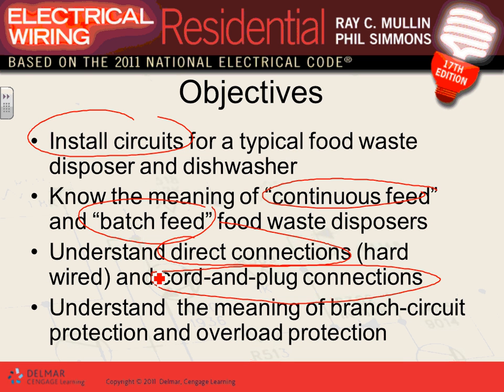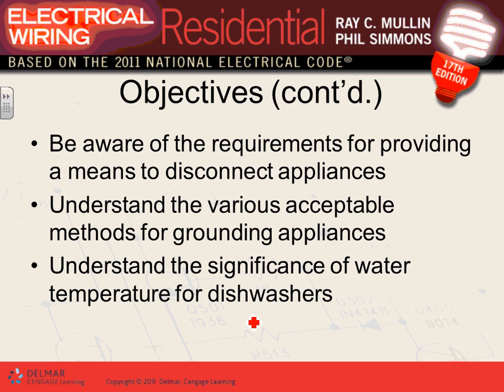And then we'll talk about the overload. Since the garbage disposal is a motor, you are to assign an overload for this motor. So around Thanksgiving, Adam, when you put all these bones in the garbage disposal and it jams, you're not going to burn it, right? The overload should trip. So that's what we're going to talk about.